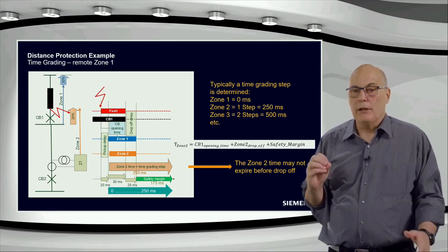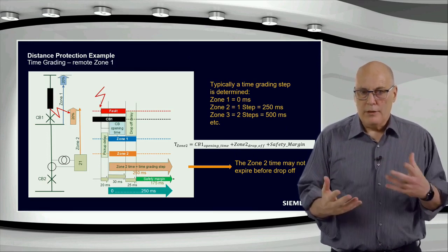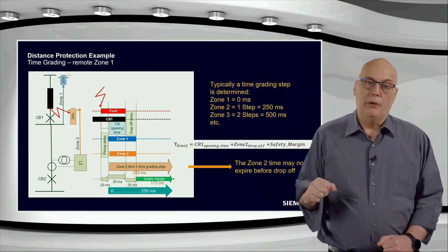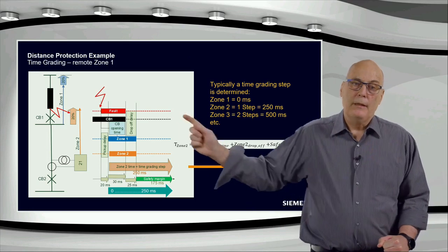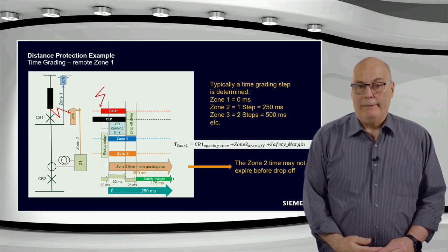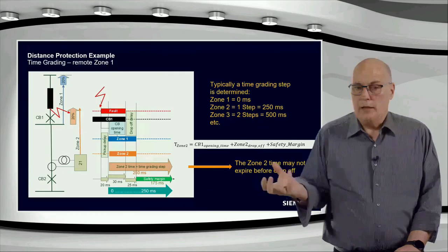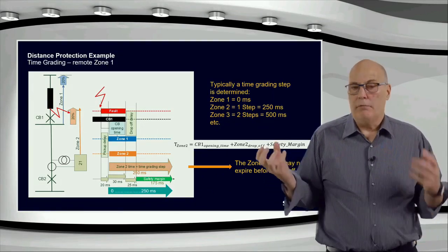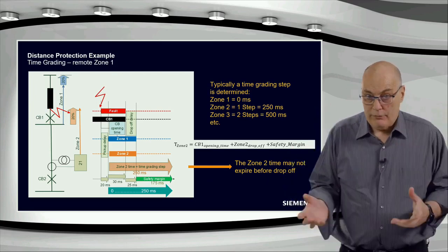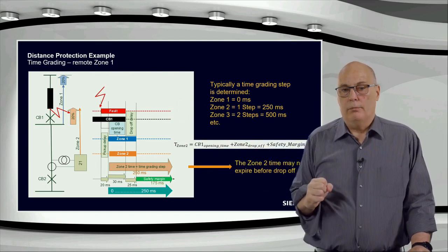The zone 2 has the function of remote backup. So what does it mean, remote backup? The distance protection generally does a very, very effective remote backup functionality. Remote backup is that if this fault that we are seeing here fails to be cleared, the relay at the top, that's zone 1, does not pick up. Maybe it's VTS failure, or maybe its contacts are breaking, or maybe the trip coils are broken, or maybe the DC has failed, or something goes wrong in a station there, and that protection fails to clear that fault.